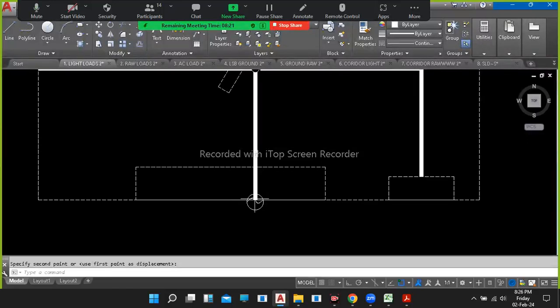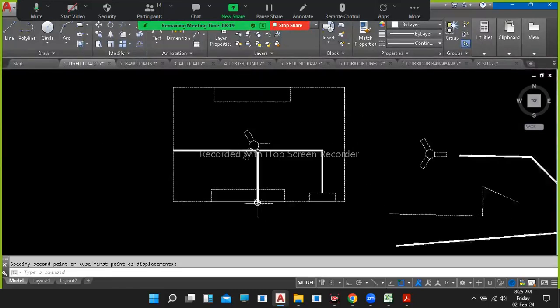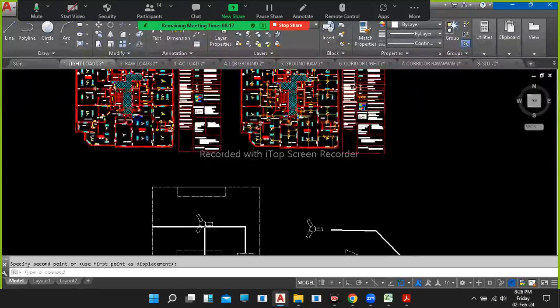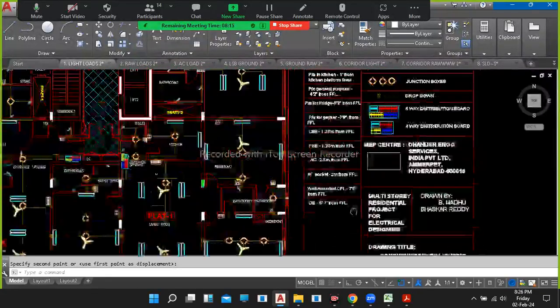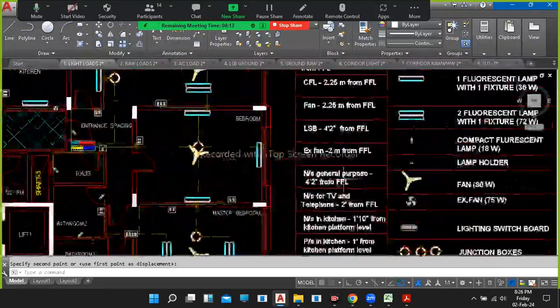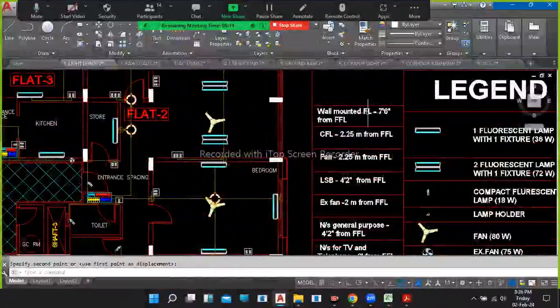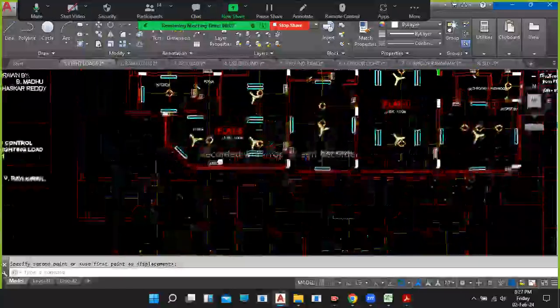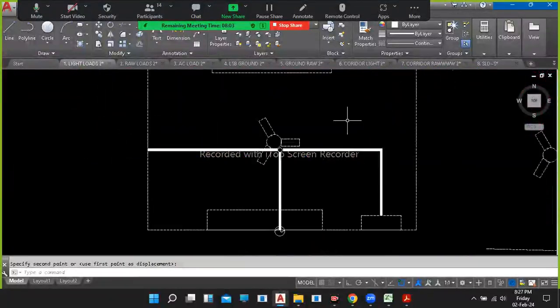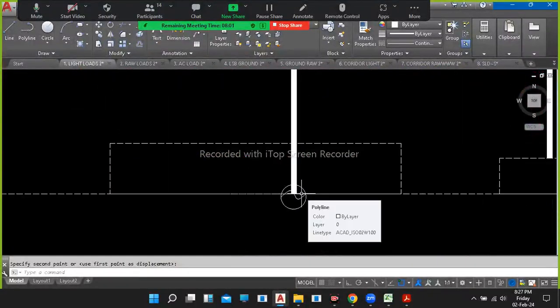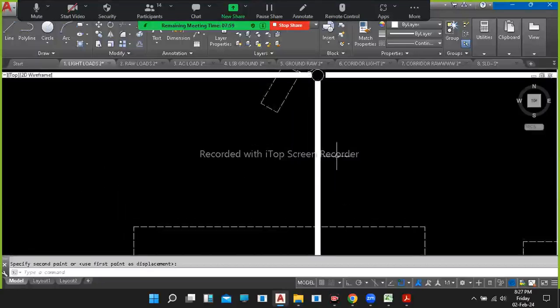So at that point we give a symbol for the drop—how much does he need to drop? He'll get that from the FL's mounted height. Wall-mounted FL height is 7 feet 6 inches, meaning leaving 7 feet 6 inches from the floor level, the remaining height is what he needs to drop the conduit.